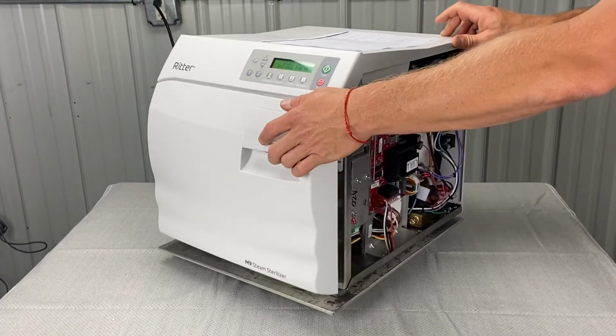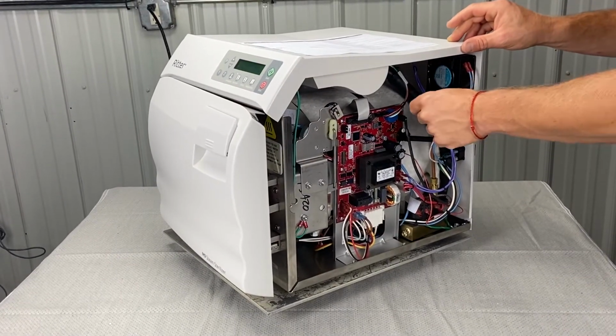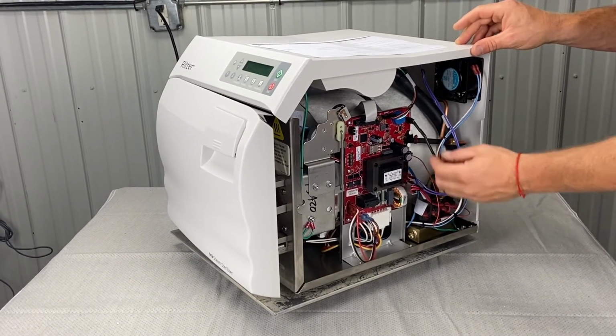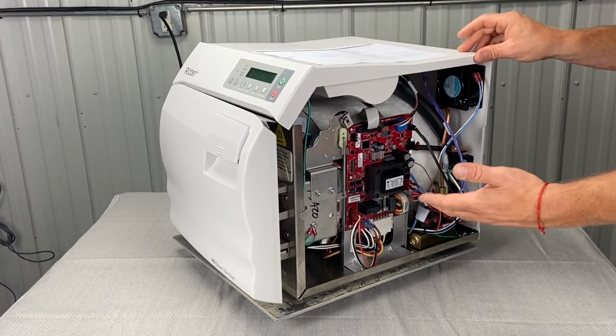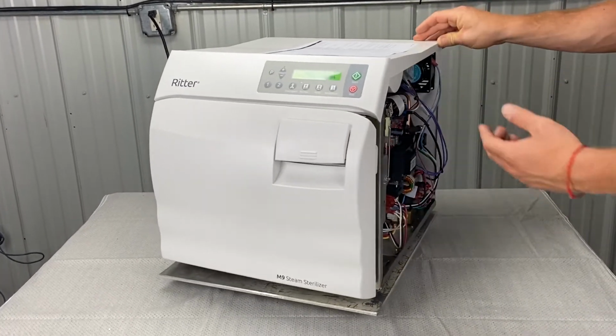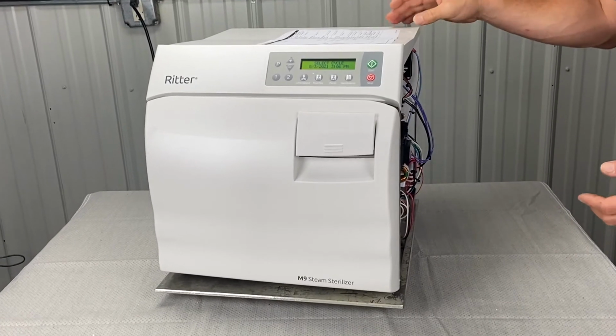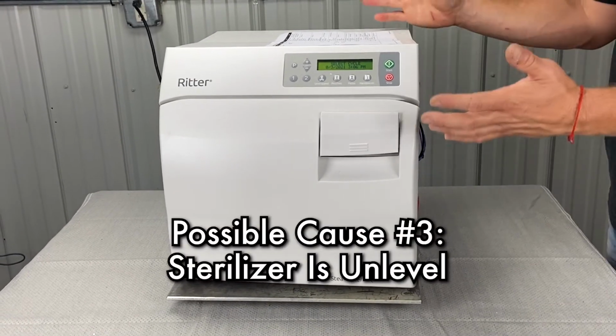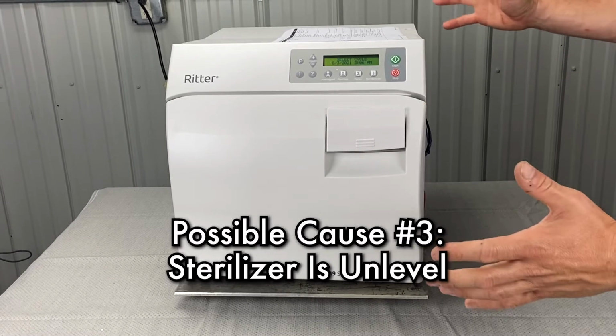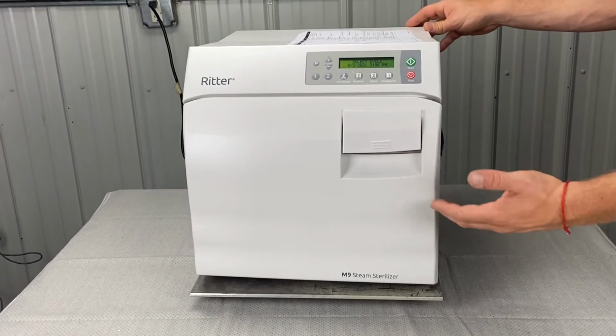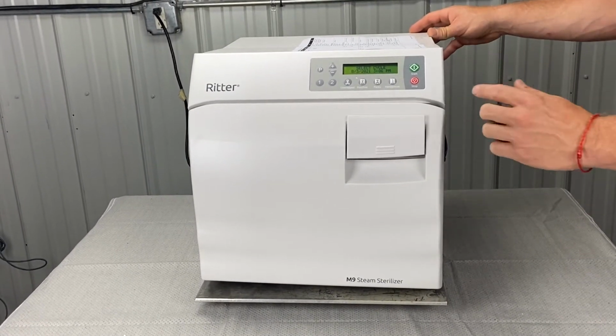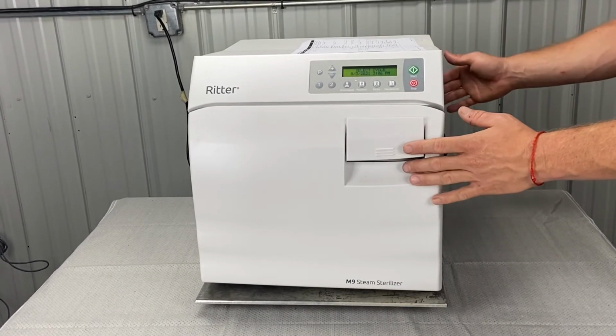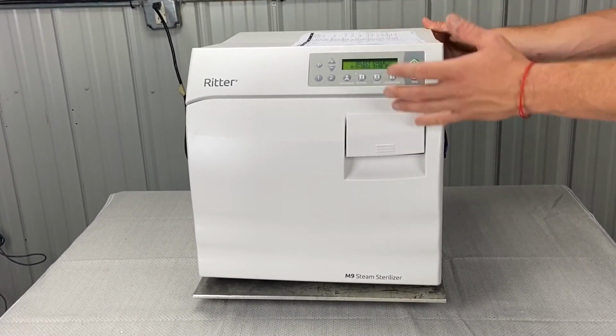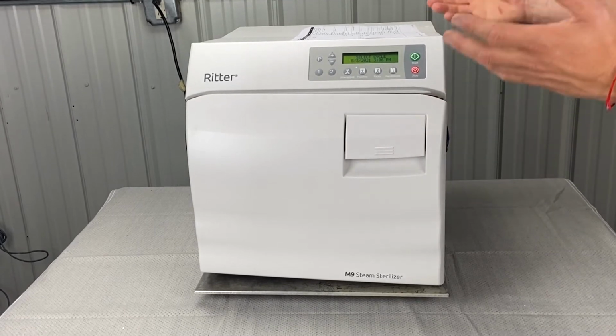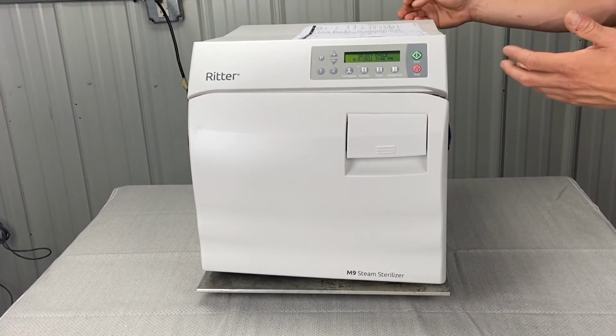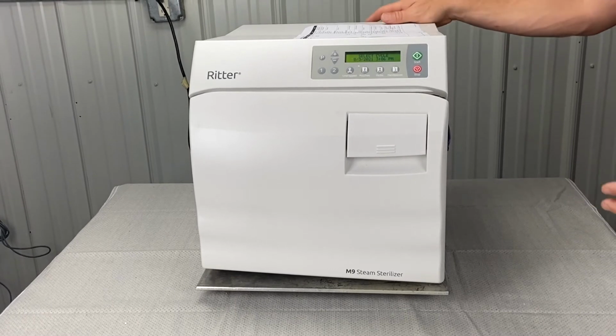Otherwise, it's a little bit more technical stuff. You'd have to get a multimeter. We unplug the temp sensor. This is the temp sensor. We unplug it. We do a resistance test. You'll need to refer to the manual for the specs of that. It could be the sterilizer is unlevel, so we want to make sure that this is level at all times. The front feet are slightly bigger than the back feet, so if you have the back up too high or the front up too high, it'll make it get either too much water, too little water. It'll overheat. It'll do all kinds of wacky stuff.